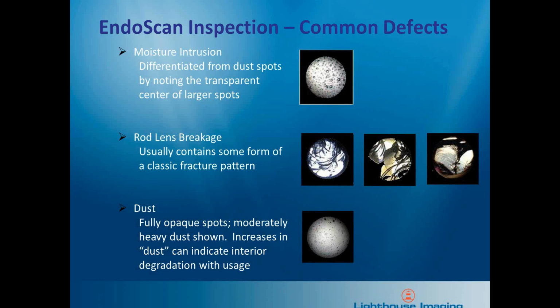And again, we'll see that in a moment, make a little more sense, I think. But here we see some sample images of moisture intrusion at the top and dust at the bottom. I should probably reorder these because I usually talk about them side by side. But you'll notice that the dust or debris inside would typically be fully opaque particles, whereas moisture would have that kind of clear in the center because it's actually a droplet forming, and then opaque on the edges. So that's kind of how you can tell the difference between whether you're seeing moisture or debris.